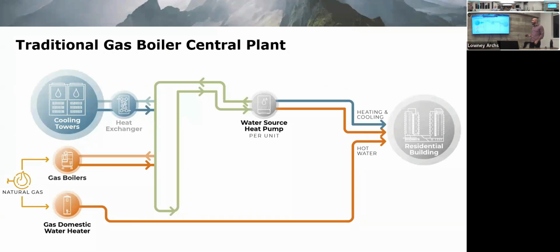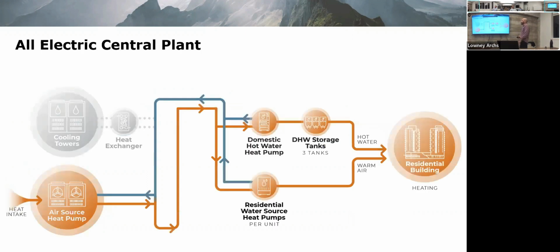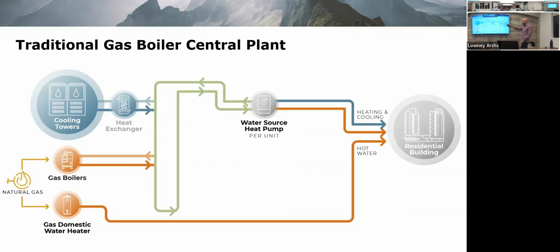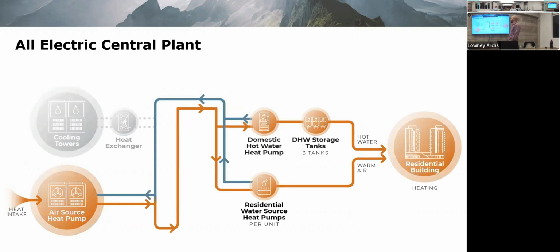In the traditional gas boiler central plant for a residential building, for instance, you would have water source heat pumps at each level, and you would see cooling towers to reject that heat, and then you would have gas boilers providing heat to the system, backup heat, and then we have a gas domestic water heater. In an electric system, the boilers basically are replaced by air source heat pumps, feeding the same system at the central level for space heating. And then you can usually have a separate air source heat pump for domestic hot water heating because the demands are different.